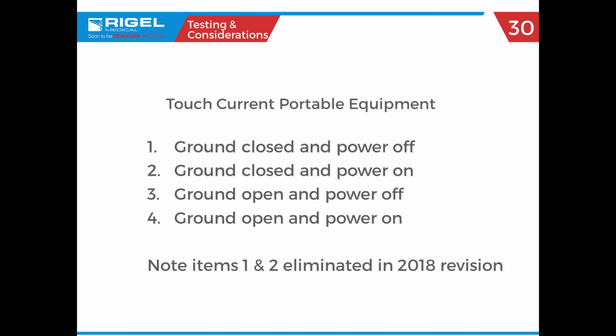So before the latest revision in 2018, you used to have to test your touch leakage in 4 conditions. So that was ground closed and power off, ground closed and power on, ground open and power off, ground open and power on. However, after that revision, it's actually only required to test the last 2 with the ground open. And so the thought process behind this was, if the unit is safe within a single fault condition, it would definitely be safe in normal operating conditions.